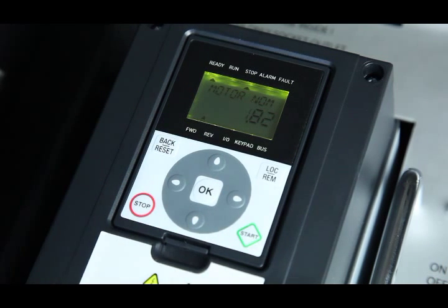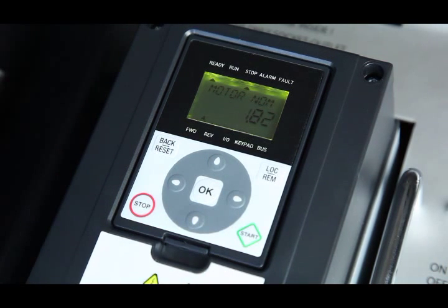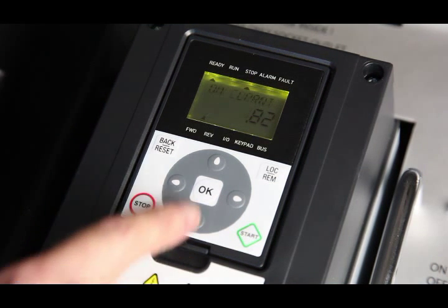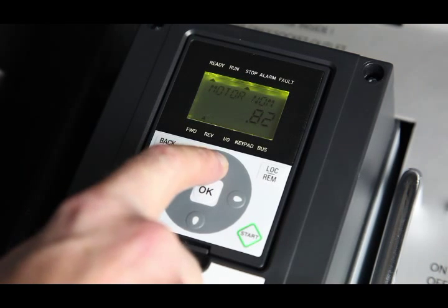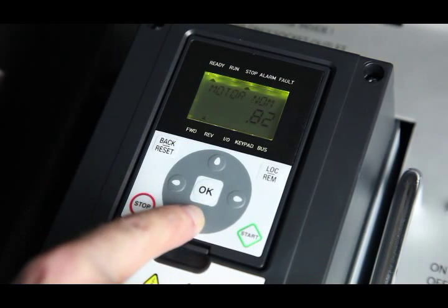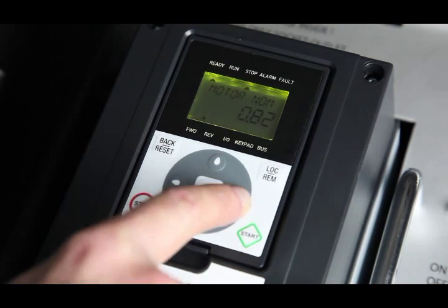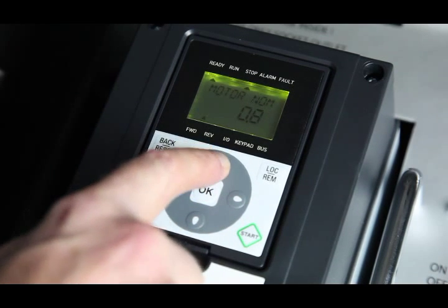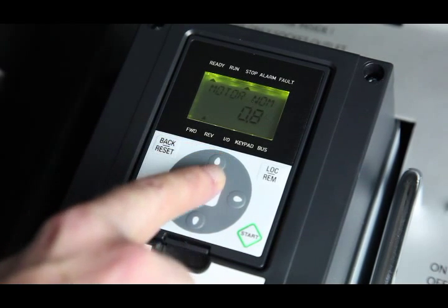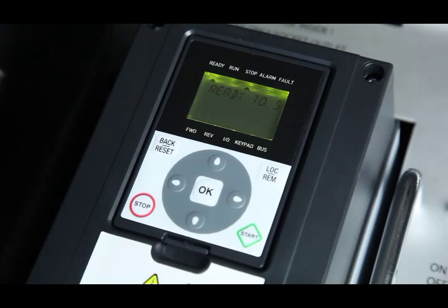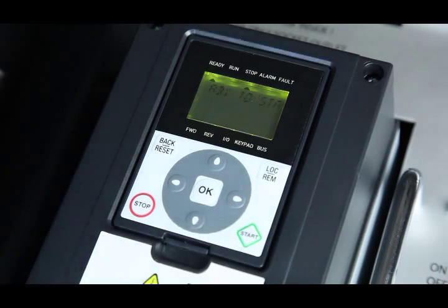It then prompts for motor current. We will now follow the same procedure as before to enter the value 0.85 amps. When OK is pressed, the display shows ready to start.